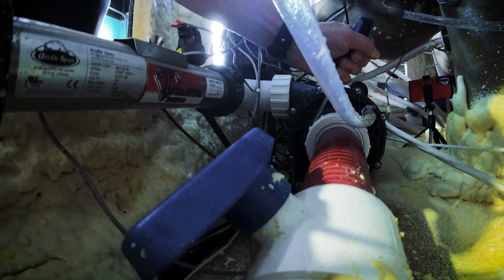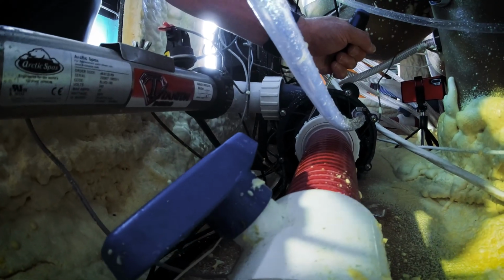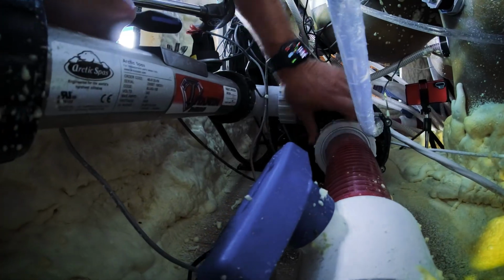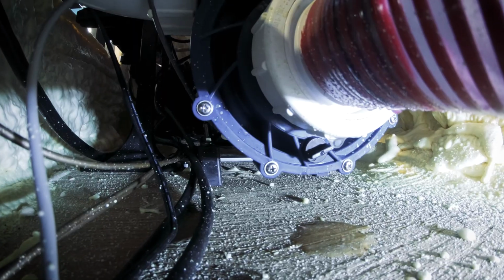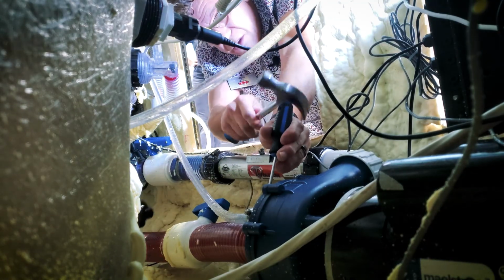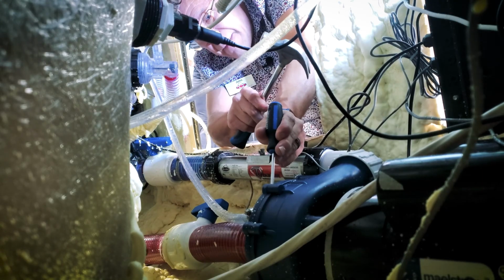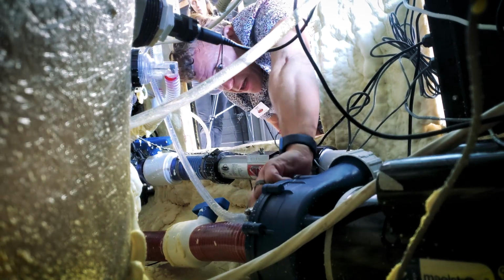Am I tightening it? No, I'm not. It should be. There, you see it moving? And then you can just tap like this and see how that union's moving around, right? And what'll happen is as I crank that further and further, eventually you can see there's some dripping right there, right? See, water's dripping out there. Now I don't want to create a big leak in the one in the showroom here, so I'm going to tighten that back up. And now my leak has stopped.